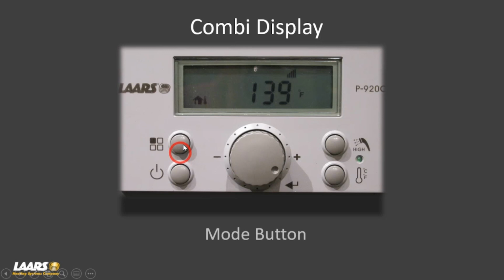Next is your mode button. In mode, this is where the installer can get in and change his parameters and set up things like an outdoor reset curve. We have a central heat button. That's where you're just going to get in and make a very simple change to your central heat. And on the combi boiler, we'll have a domestic hot water set point button. That's where you can change your domestic hot water setting for your mixing valve. On the heat-only versions, you'll have a clock symbol here, but on the combi, it's a faucet.